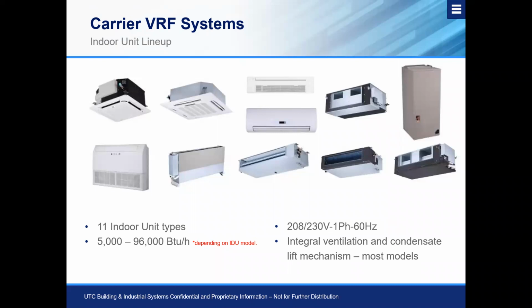Now, if we look at the high wall style units and the under ceiling floor console unit, these do not facilitate any outside air knockouts to introduce fresh air into the fan coil, and they also do not come with a condensate lift. They do have accessory style pumps that can be added to the units, but they do not come with them from the factory. The low static, mid static units have built-in condensate lifts, and they also have knockouts where you can introduce round duct into the unit itself, or you can mix in fresh air at the return, of course, because it's a ducted style unit. The only thing, just like we had with the cassette style units, is you need to make sure that that outside air is pre-treated prior to entering that fan coil. The only difference between the low statics, medium statics, and the high static unit is that the high static unit does not have a condensate lift that comes with it. So you will need to specify an outside pump, such as a Little Giant, a Sauermann, something external to the unit to manage that condensate if necessary.